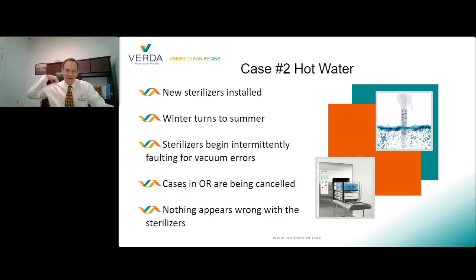All right, I want to talk about the second case study, right? This is about a hospital that installed brand new sterilizers. Now, they knew that high quality steam feed was key to successful steam sterilization. So they purchased sterilizer models with integrated steam generators designed to run off purified water. So you would have thought that they were talking to the hospital in case study one, right? And it was awesome. Everything ran great. It ran through the fall and the winter and the spring. In fact, everything ran fine for the first full year.